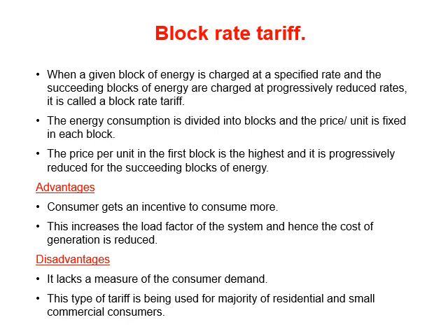So next one is block rate tariff. When a given block of energy is charged at a specific rate and the succeeding blocks of energy are charged at progressively reduced rates, it is called block rate tariff. The energy consumption is divided into blocks and the price per unit is fixed in each block. The price per unit in the first block is the highest and it is progressively reduced for the succeeding blocks of energy.